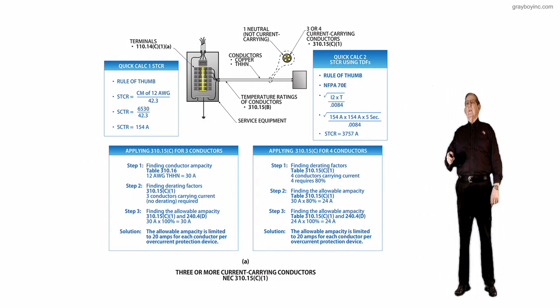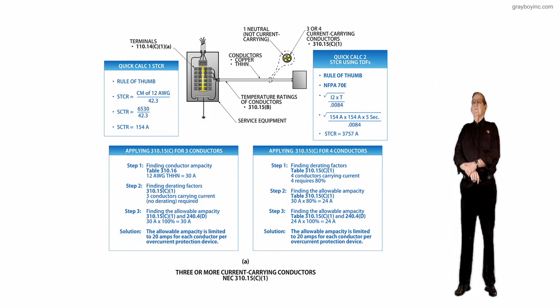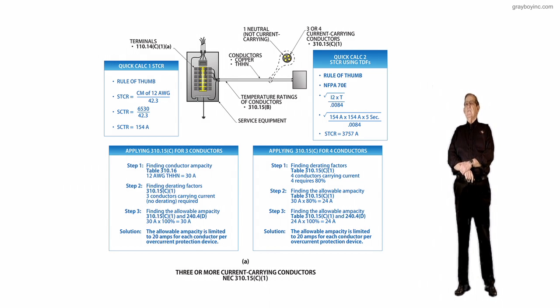And then you would take 154 times 154, current squared, times the 5 seconds for your clearing time at 154 amps. That's where this comes from, 154 amps, 5-second clearing time. With this new clearing time now, 0.0084 into that, you'd have 3,757 amps.